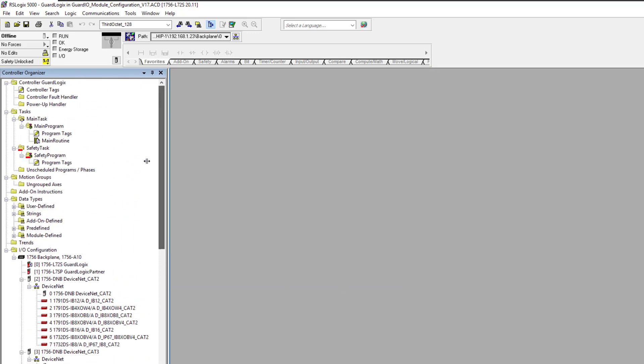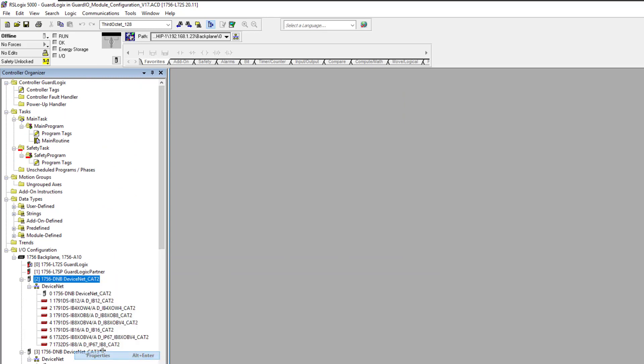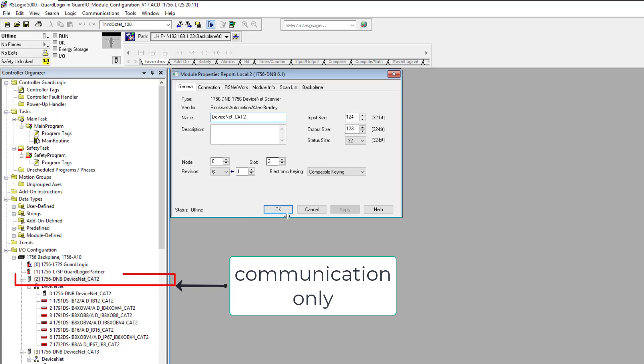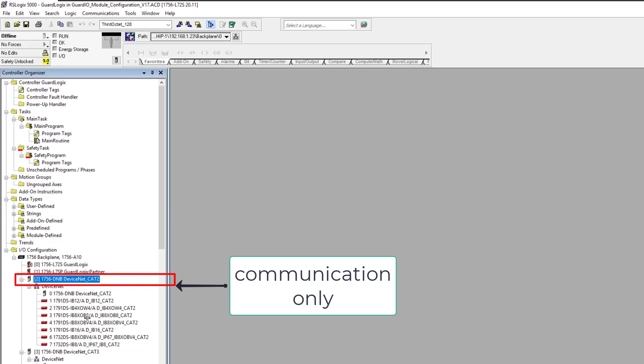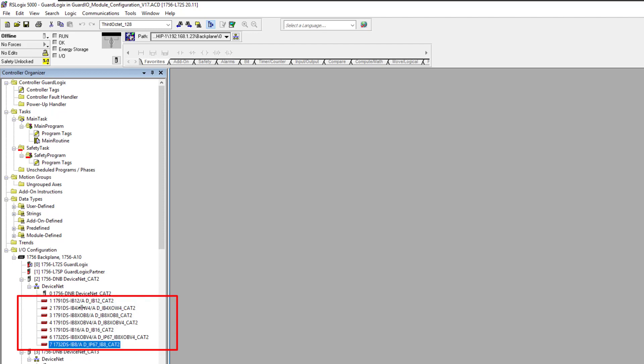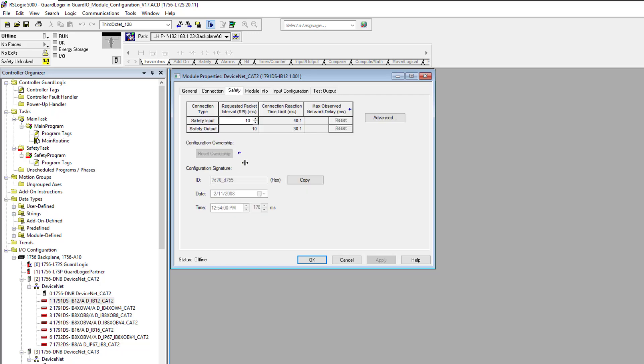When you come back here and you see all this stuff, this DeviceNet card doesn't have safety, so you could change it out. However, everything underneath it that communicates through that DeviceNet card does need to be changed because it is safety. Keep that in mind. If you change out a safety device and it's not working, it is not the device that's not working. It is the actual point where you need to go ahead and reconfigure the ownership of that device.